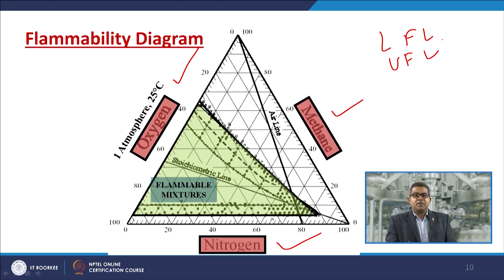Suppose I am working in a hexane environment. Definitely we do not want to have a combustible mixture, that is, the combination of hexane vapor plus oxygen. And if by any means you are not in a position to avoid such a mixture, then your attempt should be to introduce some inert so that it falls either way. Either it goes lower than the LFL limit so that the mixture doesn't form, or, if you are in a position to increase the supply of fuel, you enrich the combustible mixture in such a way that the concentration of methane is on the higher side.